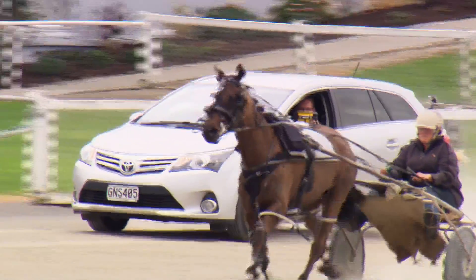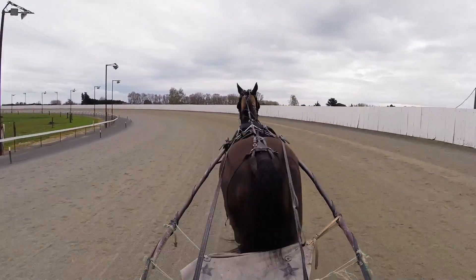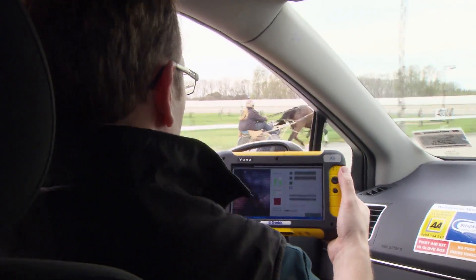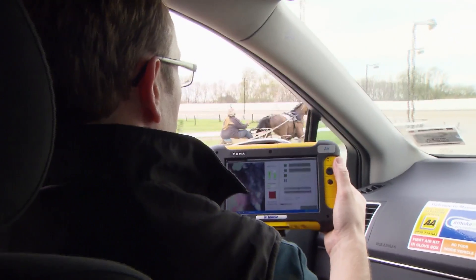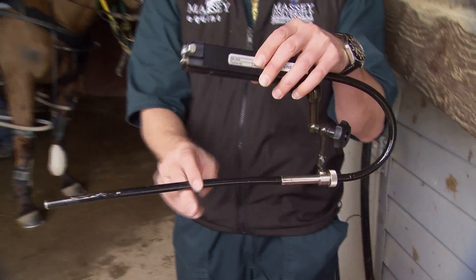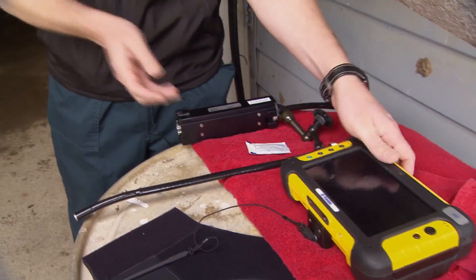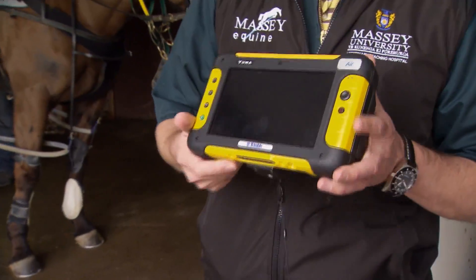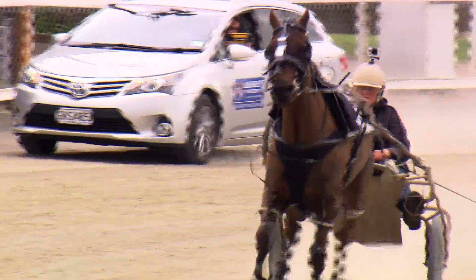The horse has to carry a laptop computer that records what we're capturing. Because it is an endoscope we have a light source, and then we have a fluid system with a pump so should we need to flush it while taking the video we can do that. We place the endoscope up the nose, and at this console we can watch the video in real time, adjust the position of the scope, flush it if needed, and watch everything as it's happening.